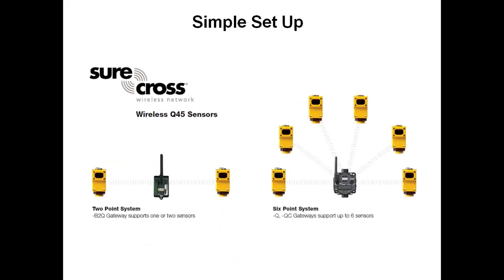Whenever we do this family, we pre-map it at the factory. So if you ordered these sensors, this gateway has 6 discrete outputs, and whenever you set this up as node 1, that's automatically mapped to output 1, node 2 to output 2, 3 to 3, and so on. You can go in and change that mapping, but this makes it simple to take out of the box and get going. You also have Modbus capability, so if you have more than 6 outputs, you can put up to 47 units out there and look at your registers via Modbus.